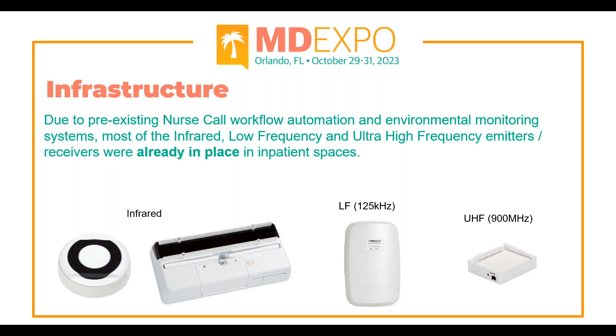So how does our system work? It all starts with these infrared emitters. They work like lighthouses and emit this infrared signal that contains a very specific location identifier. So for example, if we install this device in room 101, this battery-powered device will start illuminating the room with infrared light with a certain ID. The tag that we apply on the medical device has an infrared sensor that detects the signal and is able to communicate this information, along with its own tag identifier, via ultra-high frequency to a proprietary access point powered over Ethernet, so connected to the hospital network all over the organization.